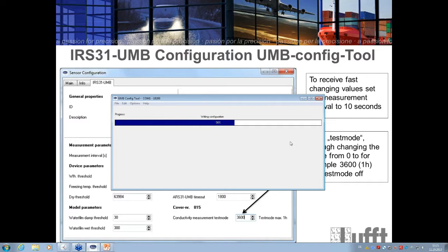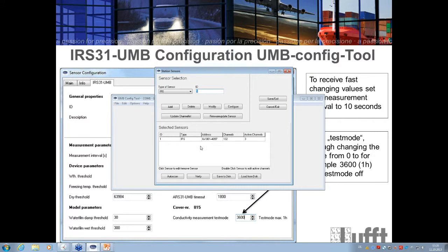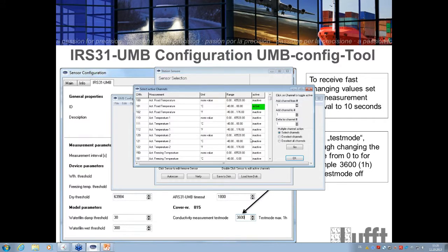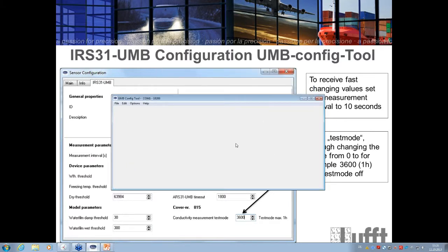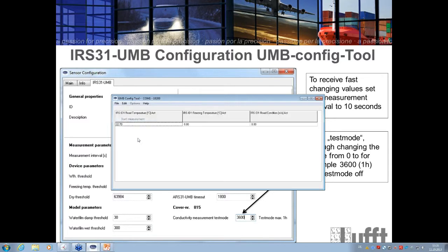You have to wait a little bit. So after that, the configuration is written to the sensor. Now the radar is deactivated. We can activate the channels we want to see, for example, again the road temperature. We do not want to see the water film. This is not important. We want to see the freezing point. So go back. It's 151, I think. Activate the freezing point and say all right. So save and exit, and now you can start with the measurement.